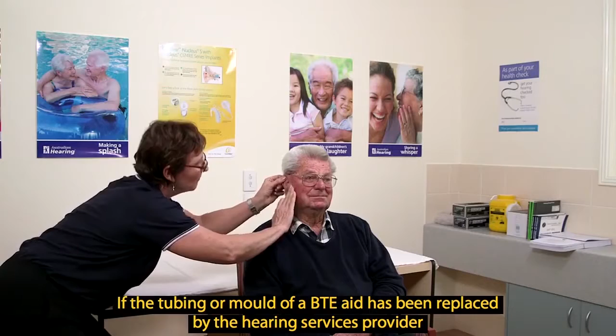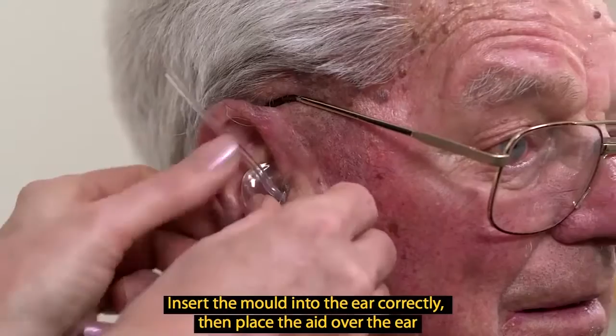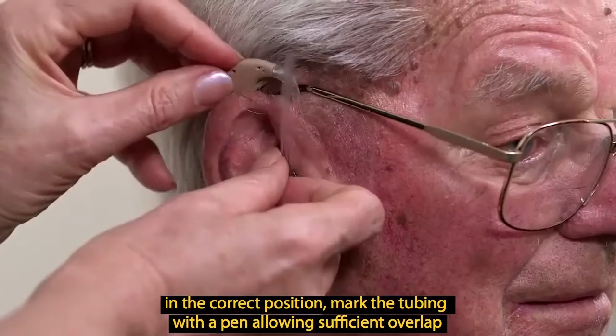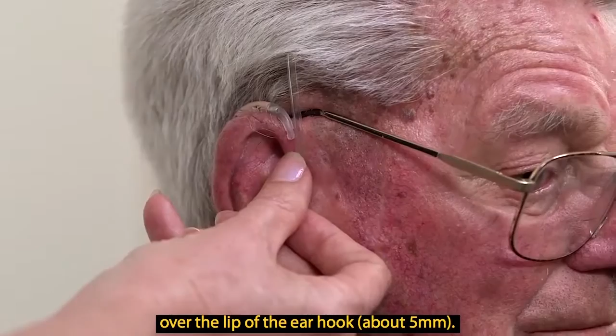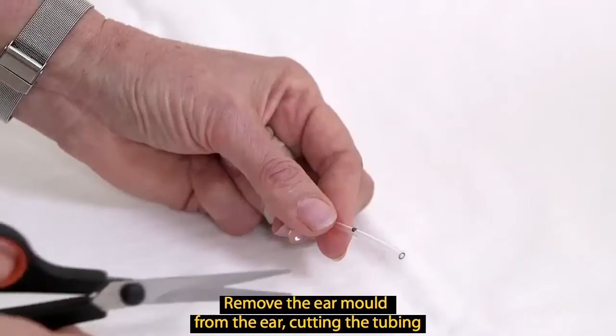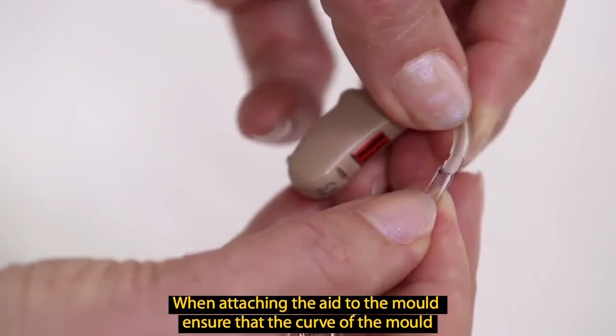If the tubing or mould of a BTE aid has been replaced by the hearing services provider, a mould with an attached length of tubing may be mailed back for reattachment to the aid. Insert the mould into the ear correctly, then place the aid over the ear in the correct position. Mark the tubing with a pen, allowing sufficient overlap over the lip of the ear hook, about 5 mm. Remove the ear mould from the ear, cutting the tubing on the higher side of the mark. Do not cut the tubing whilst the mould is in the ear. When attaching the aid to the mould, ensure that the curve of the mould matches the curve of the hearing aid.